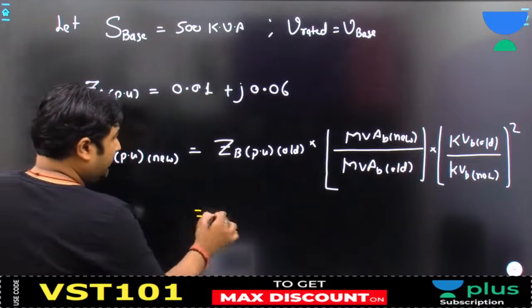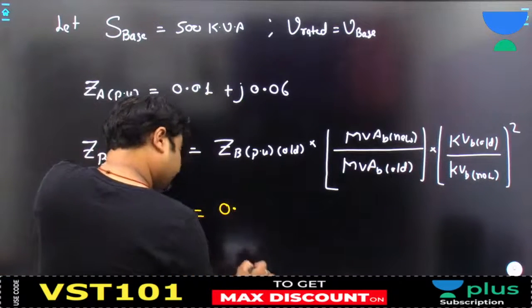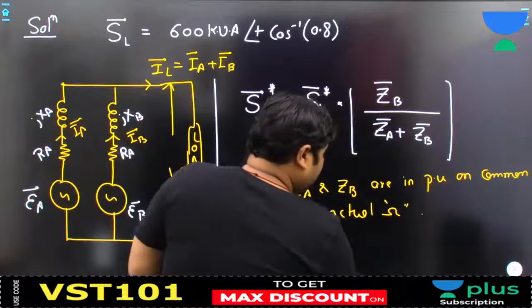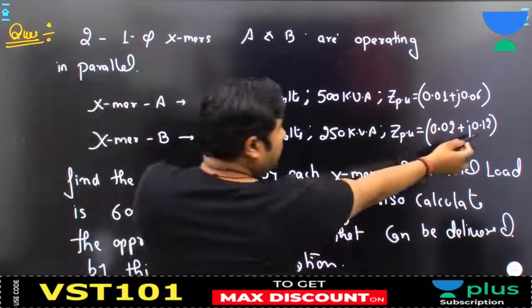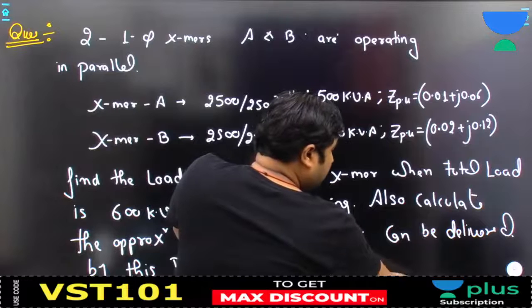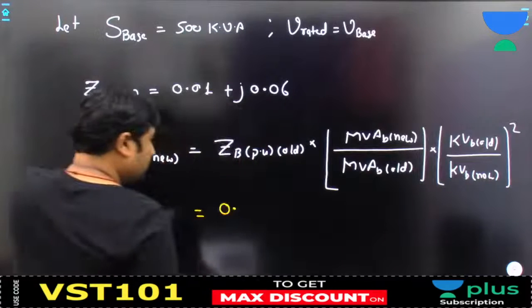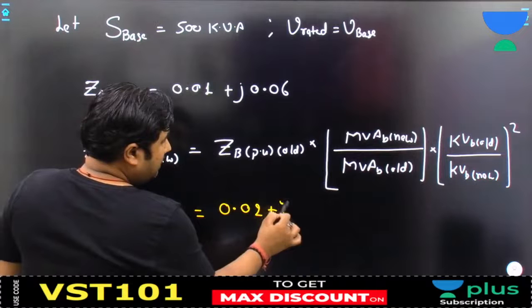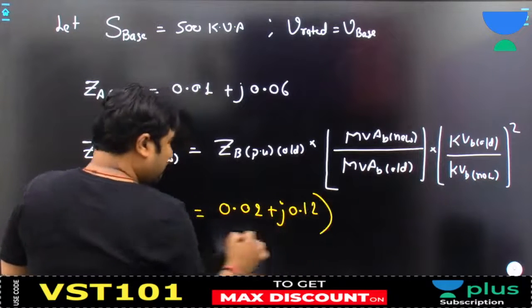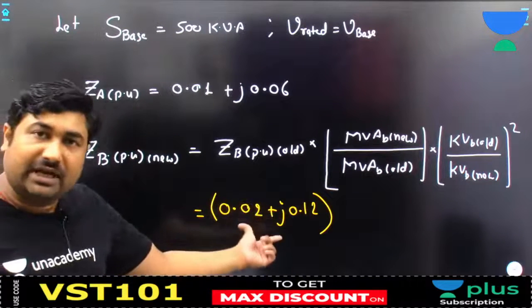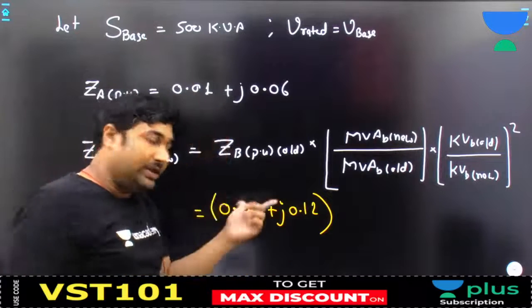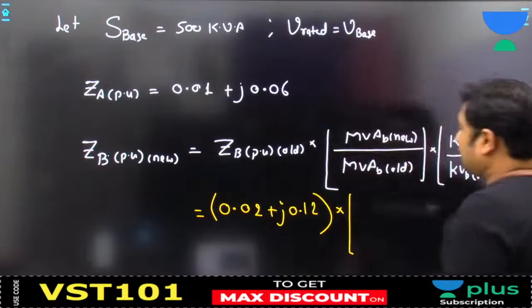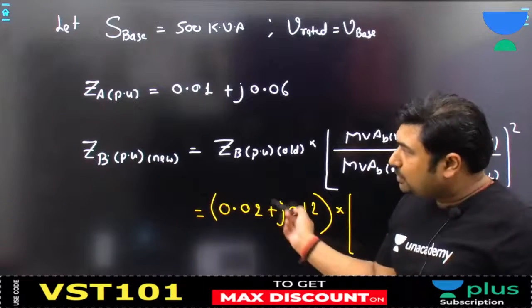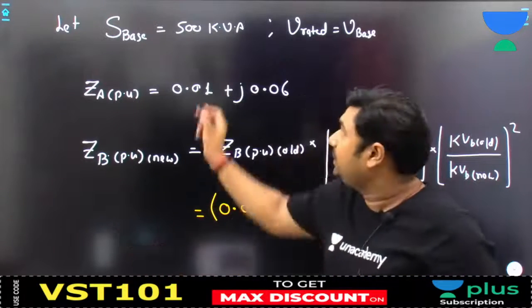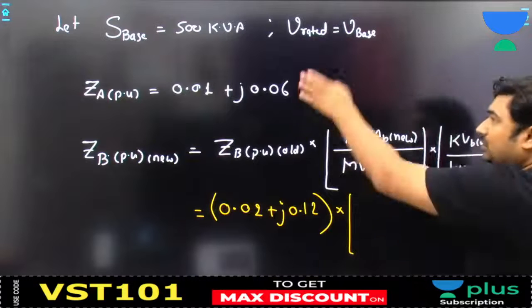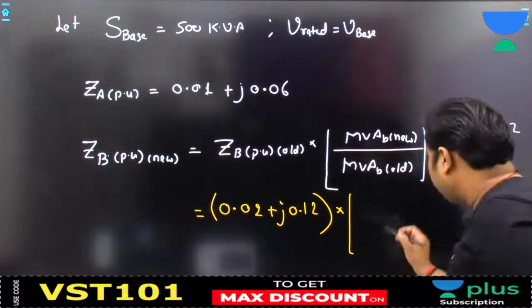Now please observe here, Z per unit is 0.02 plus j0.12. So 0.02 plus j0.12 is the previous per unit value based on the transformer B rated values selected as the base value, and now I am going to find the new per unit values on a new base. Is it okay? So both per unit impedances are going to be on the common base.